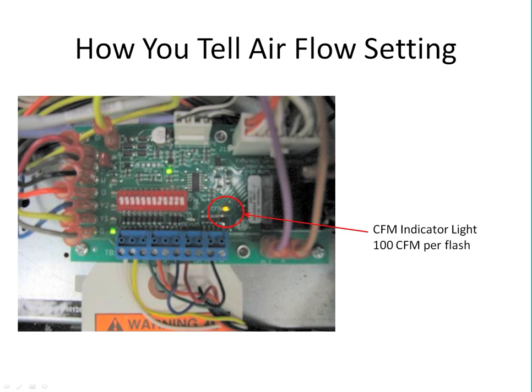If you need to adjust that, or even if you have the dehumidification dip switch set and you saw that light lit up, you need to take it out of that mode for this test. So if you need to change that fan speed or take it out of the dehumidification mode, remember, before it will notice and secure that new CFM range that you just selected, you have to power the unit down for at least 3 seconds before it will pick up that fan speed change. So make sure that you do that. It's an important part, and you can't miss it.